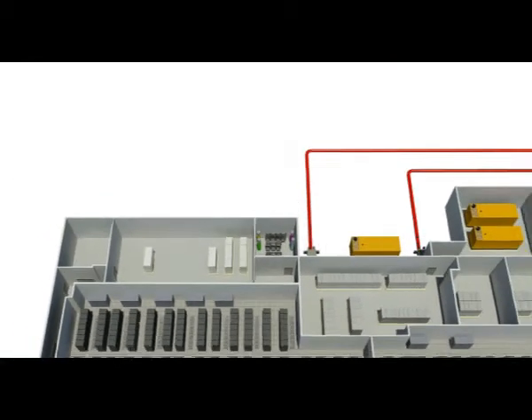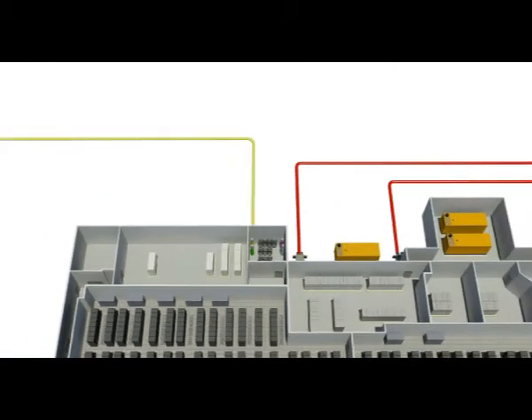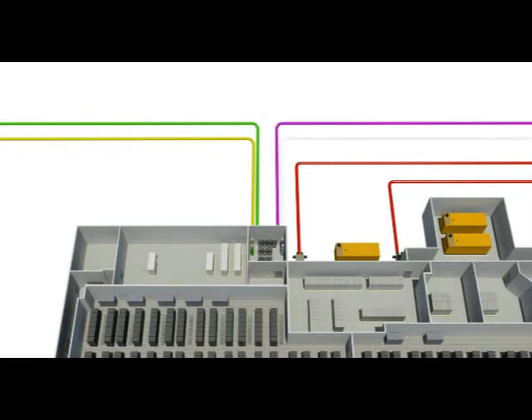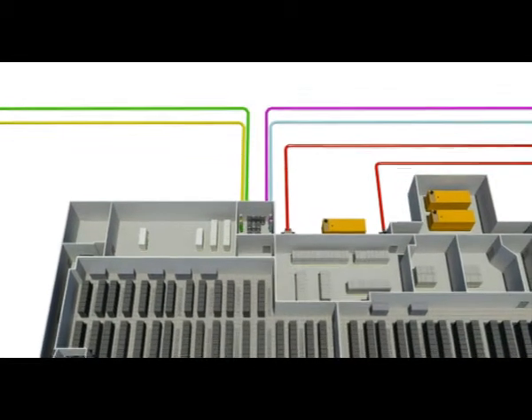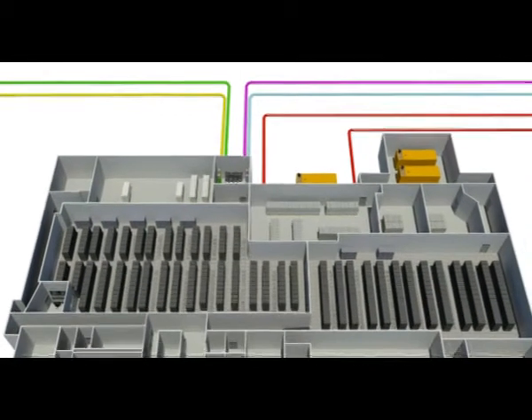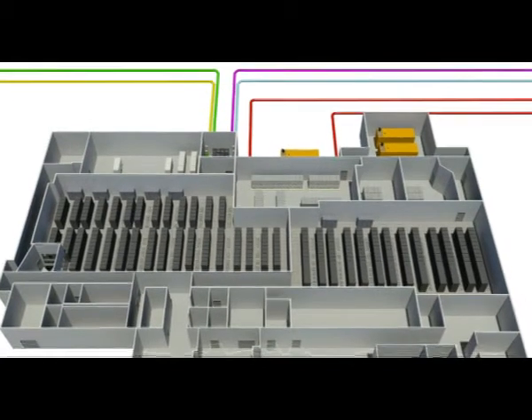Fiber optic connectivity is delivered to the building through a diverse routing from 4 diverse fiber optic conduits into the data center's hub for connectivity, the POP room. From there it is fed into the Meet Me room and then distributed for use. This mesh configuration eliminates single points of failure and provides uninterrupted data flow across the network at all times.